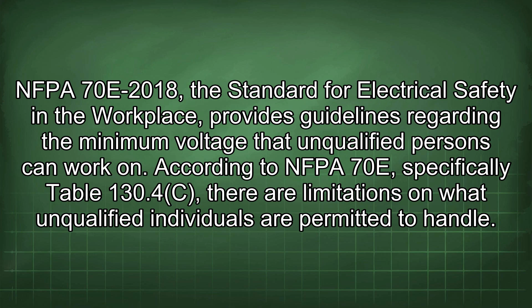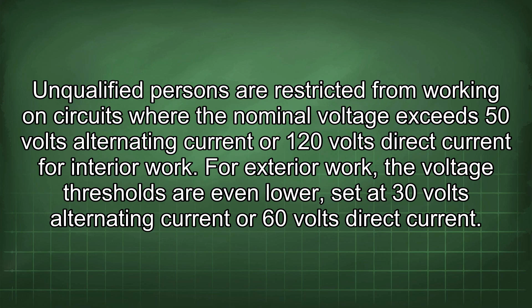Unqualified persons are restricted from working on circuits where the nominal voltage exceeds 50 volts alternating current or 120 volts direct current for interior work. For exterior work, the voltage thresholds are even lower, set at 30 volts alternating current or 60 volts direct current. Furthermore, unqualified persons should not work on circuits protected by more than 600 volts between conductors.